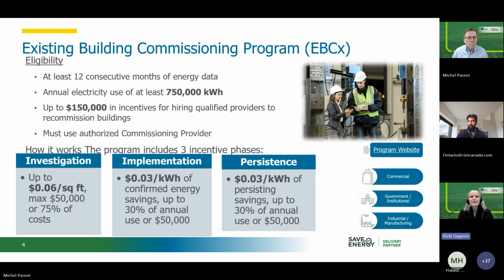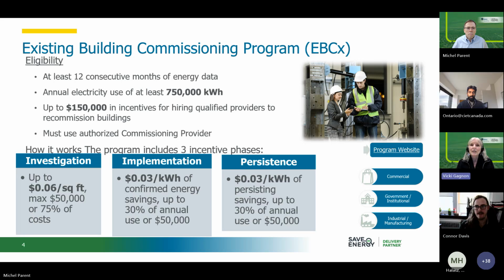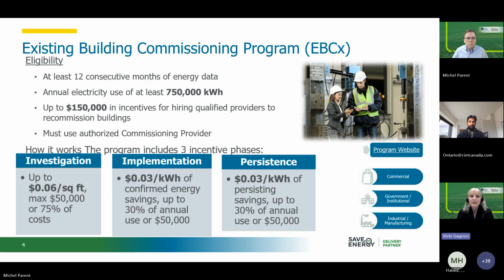First is the existing building commissioning program, and it helps you get your building back to working the way it was originally intended and to optimize the facility operations and maintenance practices to improve building performance. There are incentives of up to $150,000 for hiring a qualified commissioning agent to recommission the buildings. The incentives come in three phases. The first is the investigation phase, to hire a commissioning agent to help identify the areas to optimize, and that's at 6 cents a square foot.